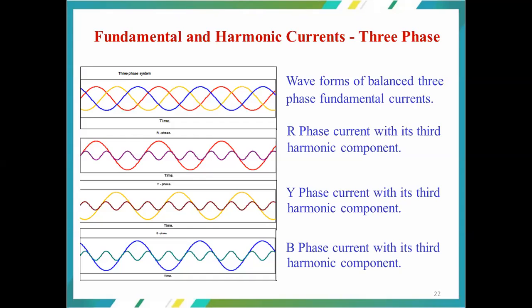So these are the fundamental and the harmonic currents, three phase. The first one is the 50 Hertz three phase RYB sequence, and the second one is the R phase with its third order harmonic component. The waveform marked in red is the fundamental component, and the waveform marked in purple is the harmonic component. When the fundamental component passes a single cycle, the harmonic component passes 3 cycles. Hence, it is called a third order harmonic component. Likewise, the Y phase has its own fundamental and third order harmonic component, and the B phase has its own fundamental and third order harmonic component.